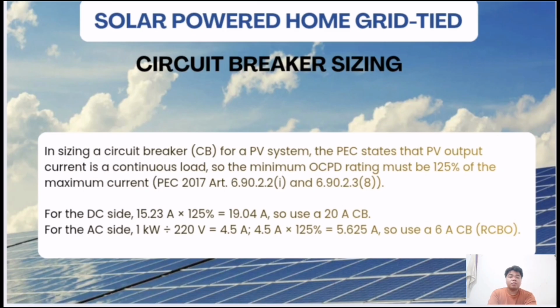Dahil dito, kinakailangan natin i-apply ang 125% safety factor upang magkaroon ng allowance sa design at masiguradong safe at stable ang operation ng system. Para sa DC side, based sa computation mula sa solar panel, ang maximum current ay 15.23 amperes upang makakuha ng tamang breaker size. I-multiply natin ito sa 125% safety factor. 15.23 times 1.25 equals 19.04 amperes. Dahil sa standard breaker ratings na available sa market, walang eksaktong 19.04 amperes. Kaya sa actual installation, pipili tayo ng nearest standard size na mas mataas sa computed value. Sa kasong ito, ang napili ay 20 amperes circuit breaker upang masiguro ang sapat na protection ng hindi magkaroon ng nuisance tripping sa normal operation.